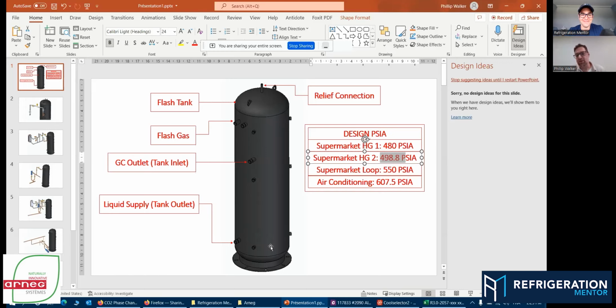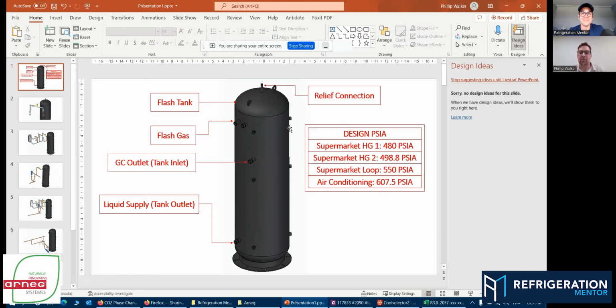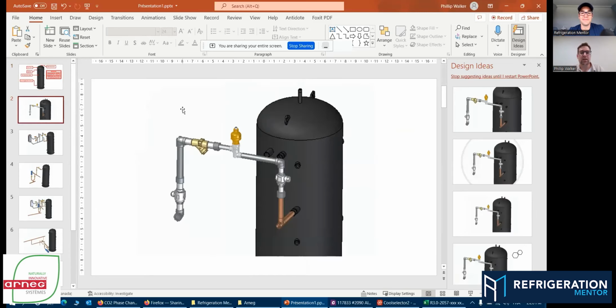And so if this is exposed by any means, and we've done a few projects on some of the older systems out there, where we've come in and the team has brought it up to speed, the insulation is wearing off. You'll have a significant amount of condensation occurring on the flash tank. And that condensation will cause an effect on the older design flash tank. So just a little caveat to think of. Insulation goes a long way. If you're seeing a lot of rusting and water pooling down at the bottom, maybe you're missing out on some insulation down onto the base, something to take a look at. It's going to help with your design. That's a great tip.